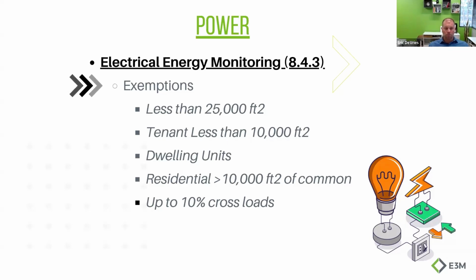Dwelling units are excluded. So if you build your condo building, you've got to monitor the hallways off of a common house panel, but your condos, your apartments, your dwelling units themselves would be excluded. Residential only applies if the common area is larger than 10,000 square feet. So you build that apartment, right? And you've got a small little corridor on each floor. If the combination of those corridors and maybe your mailroom and your lobby is less than 10,000 square feet, you can be exempted from this.